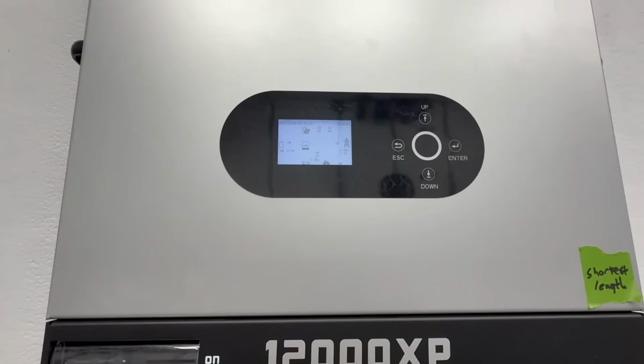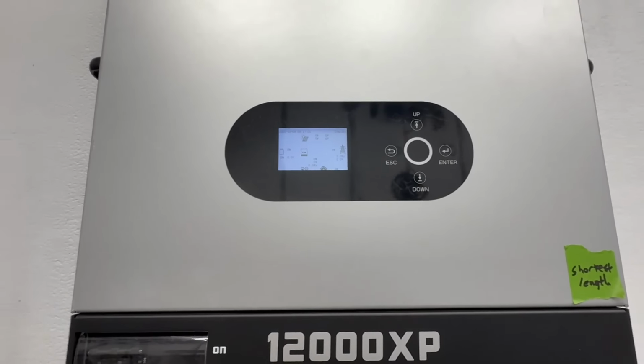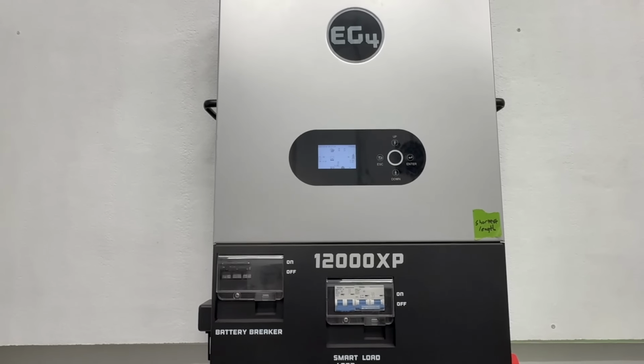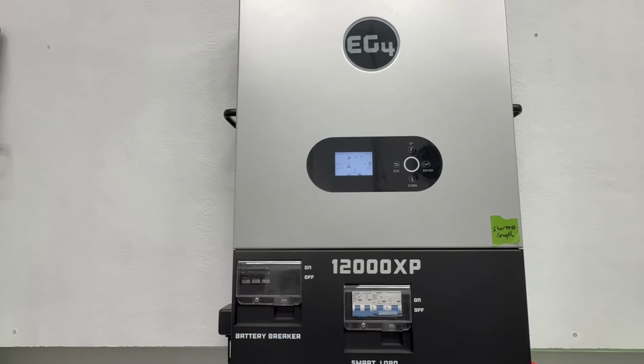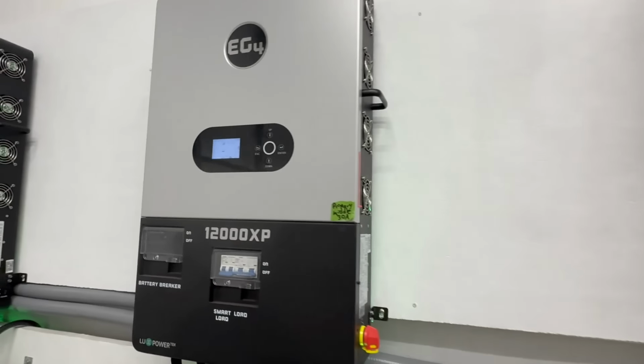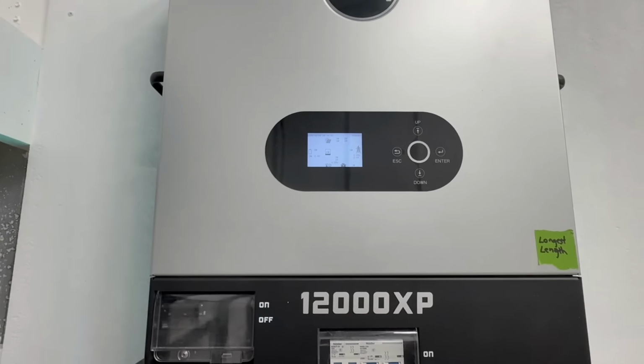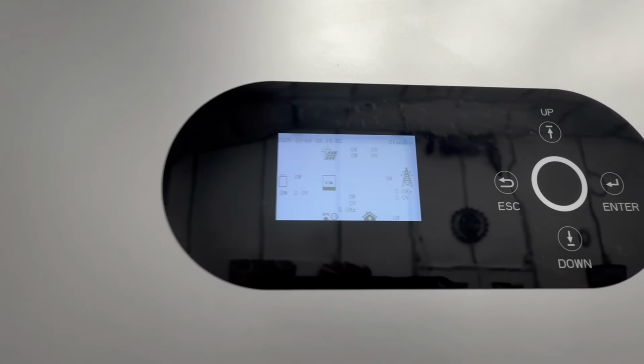If memory serves me correct, I should have a nice yellow ring instead of the green ring I have on that one, because I need to set it up in lead acid mode, whereas by default it's in SOC mode and trying to communicate with batteries that don't have communication set up. So here's what it's showing so far: 0 battery voltage, because it doesn't know yet, since I've got to set it up for lead acid. But they are all powered up.